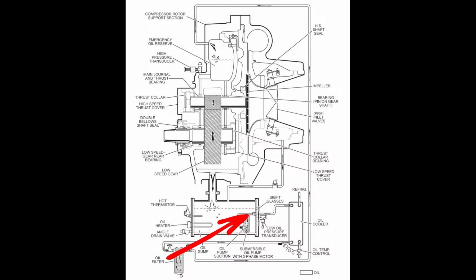Sensors in the front, doesn't look like 180 degrees is the trip point. Right. Oil level is about 85% glass. Okay, so getting back to, we have to make sure we have enough oil. That's the next thing. 85% of the sight glass, I'm happy with that.